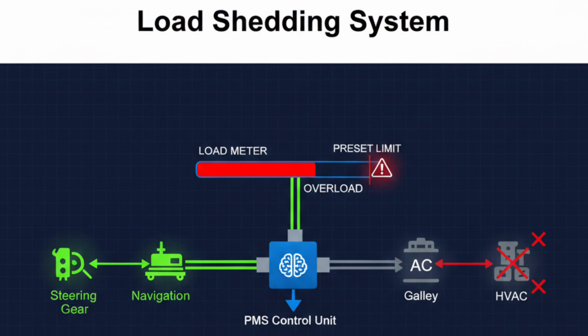If the total demand exceeds the available generation, PMS prioritizes essential equipment like steering gear, fire pumps, emergency lighting, and navigation systems. Non-essential loads such as air conditioning, galley equipment, and non-critical cargo systems are disconnected temporarily. This prevents a total blackout while keeping the ship's vital systems operational. The system reconnects non-essential loads automatically once the load stabilizes and generation is sufficient. Load shedding is an essential part of PMS, ensuring ship safety, operational continuity, and minimizing the risk of catastrophic power failure.